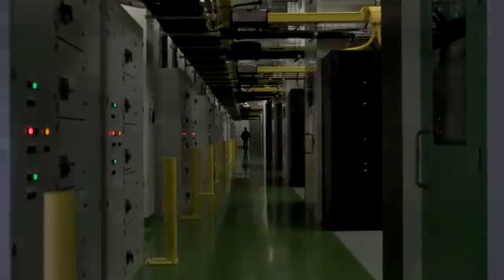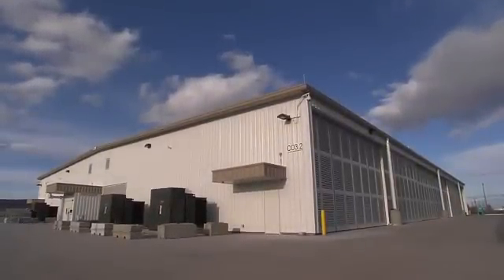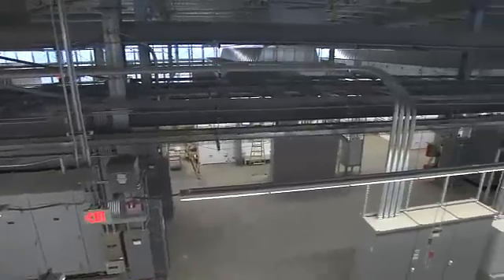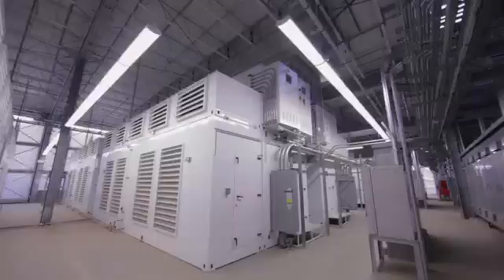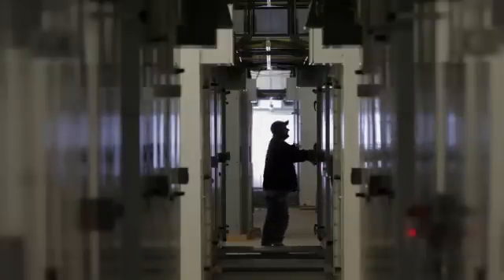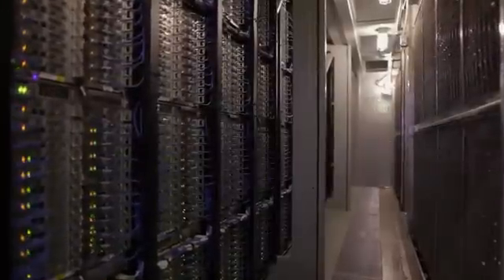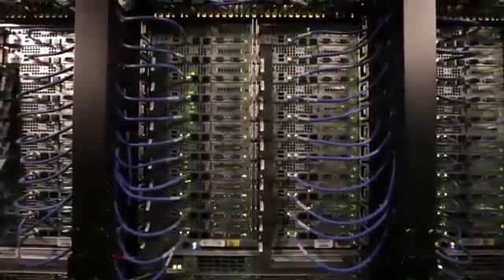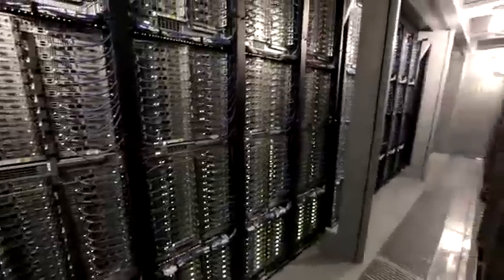In 2010, we began to build our first Generation 4 data center design, building on the Dublin experience of air-side economization into a truly modular design. This technologically advanced facility challenged every industry design standard to significantly reduce water and power use. Our Generation 4 facility utilizes air-cooled IT pre-manufactured components, or IT packs — state-of-the-art pre-assembled plug-and-play modular components that can be manufactured in many locations through a dynamic supply chain of globally distributed vendors, using recyclable materials such as steel and aluminum. IT packs allow rapid commissioning of additional compute capacity, reducing the typical two-year construction timeframe in half and reducing capital costs by 30 to 50% over the lifetime of the facility.